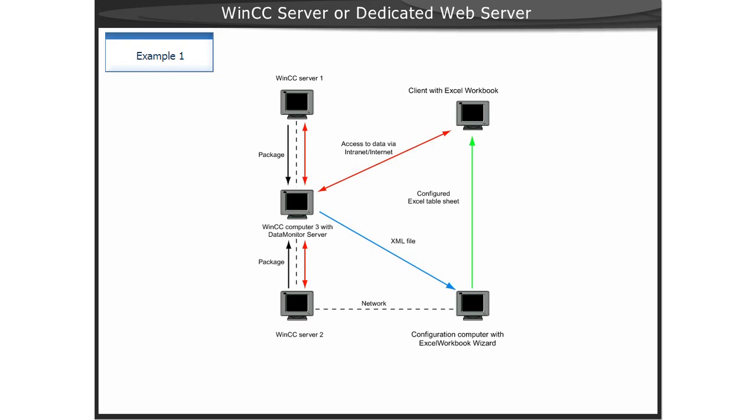Therefore, no XML file is required for this project. In order to access process data on the subordinate WinCC Servers 1 and 2, the name of the computer whose process data is to be displayed is specified as the Server prefix.